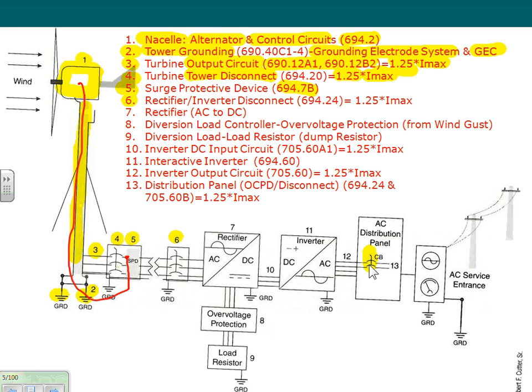In the solar system, we have only an inverter, so they have a DC disconnect and also an AC disconnect, and that's required by code. So how do we size this? That's always my concern. The same thing: 1.25 times the maximum current. Then if you look at 4 and 6, if they're within sight, they could be the same disconnect for the inverter. Your inverter might be inside the building, and that's why you have to have a disconnect. But if the inverter is right next to the equipment, then that same disconnect, 4 and 6, could be the same piece of equipment. So they play with where you put these. Make sense for the electricians? And so that's your inverter.